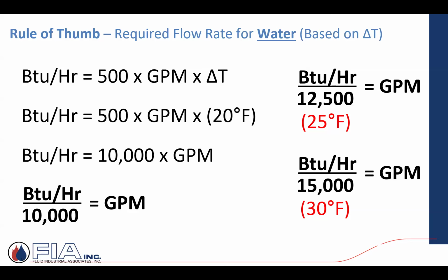Flow rate? That's a great question. The question asked in the classroom was, why wouldn't we just pick the highest possible delta T, which would result in the lowest required flow rate? It is a design consideration. One of the concerns would be, and I'm just going to give you an example and we'll work through it. If I send out water temperature at 180 and I allowed an 80-degree delta T, so now I'm coming back at 100.